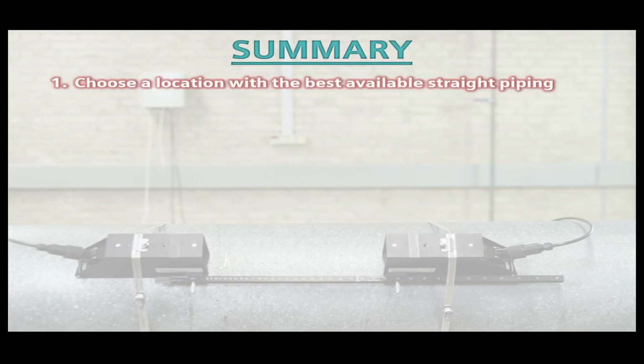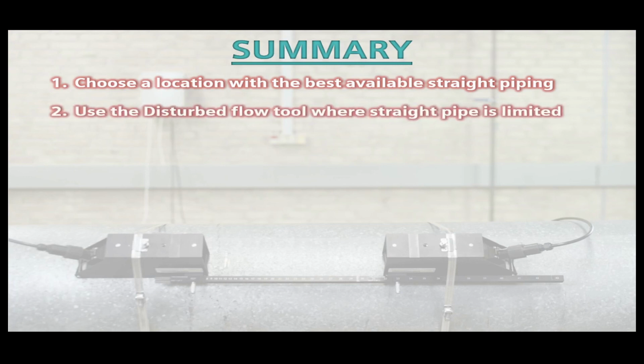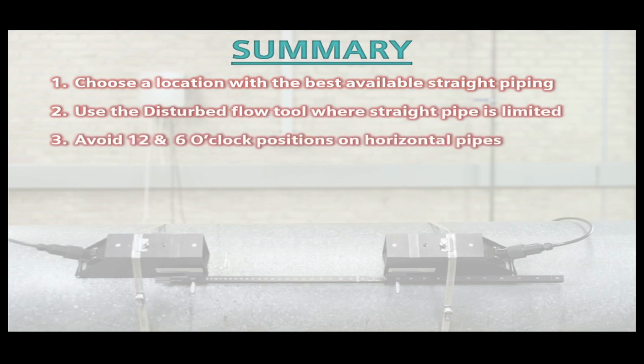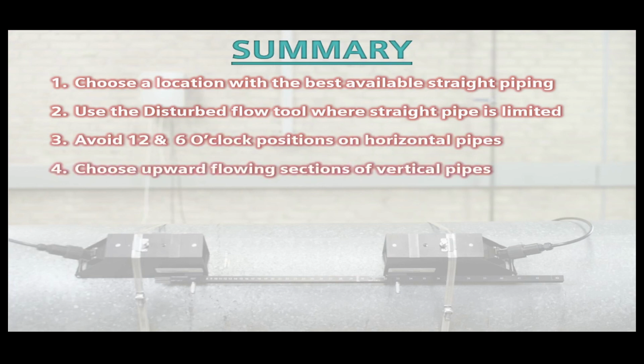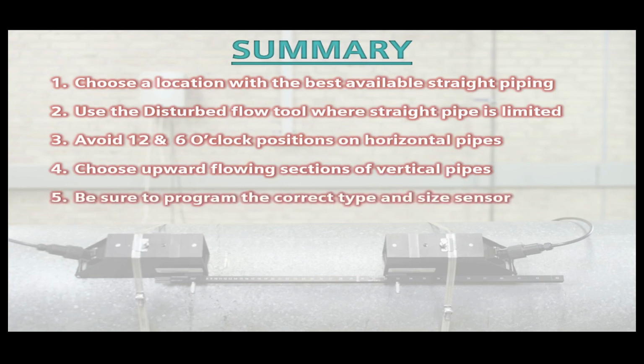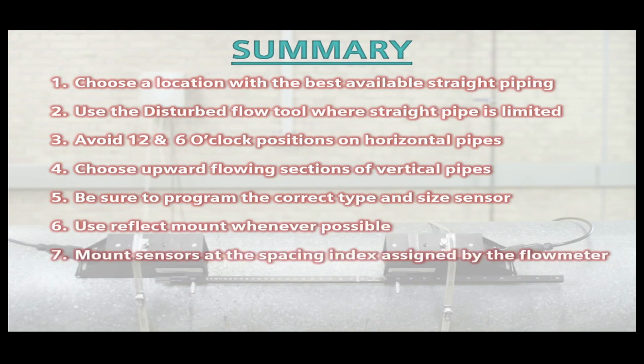So to summarize what we've covered, choose a location with the best available straight piping. If straight pipe is limited, use the disturbed flow tool you find in the flowmeter menu. Avoid mounting your sensors at either the 12 o'clock or 6 o'clock positions of horizontal pipes. Choose upward flowing sections when installing on vertical pipes. Be sure to program the correct type and size sensor. Use reflect mount whenever possible. Mount the sensors at the spacing index assigned by the flowmeter. And finally, relax. You can do it.